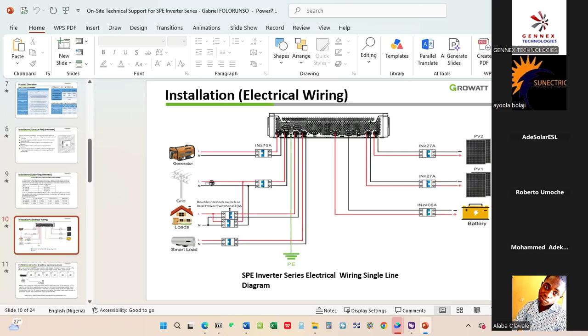To program it, we use program 23 to make it work in parallel, either single phase or 3-phase. By doing so, one of these inverters ends up as the host or master inverter. The BMS port on the host inverter will now be linked with the battery via a LAN communication cable to establish proper communication between the two.